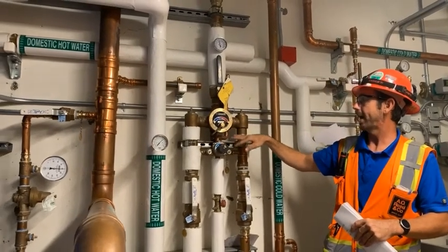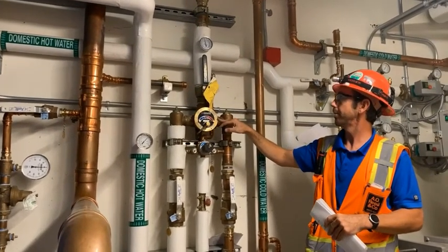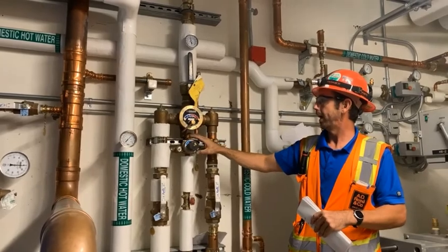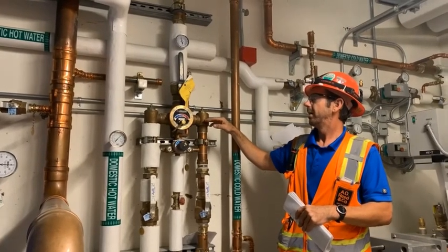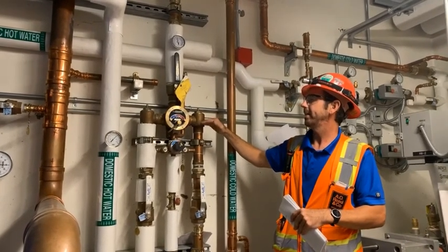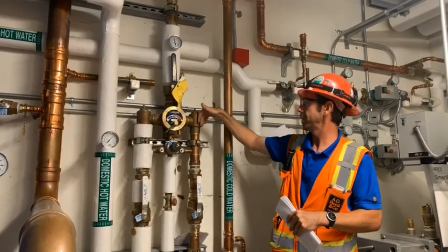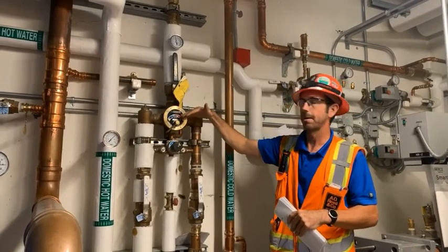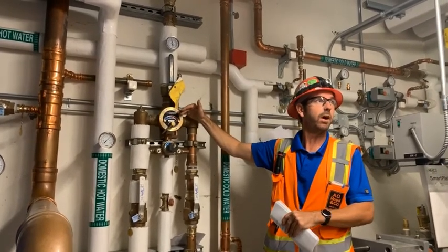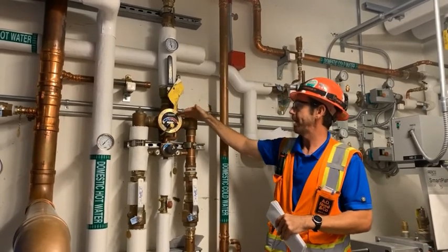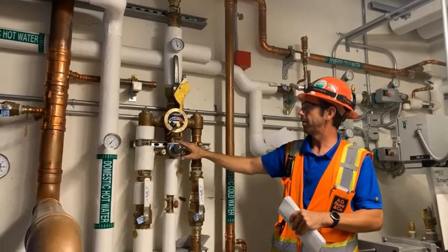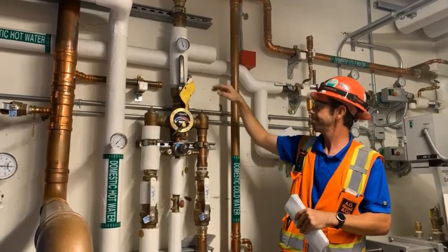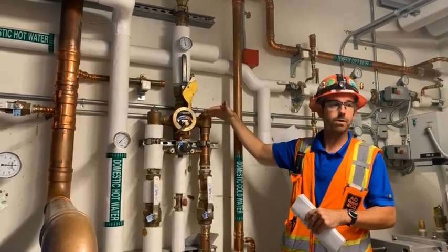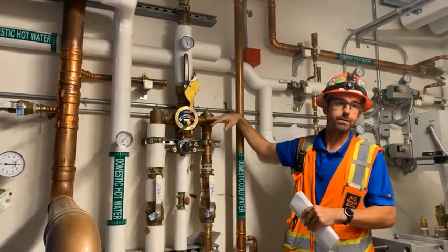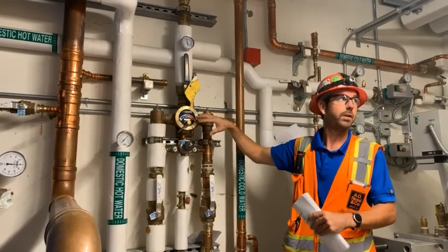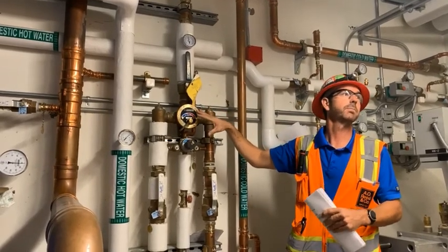This is kind of set up as a high flow, low flow thermostatic mixing valve. Under, I believe it was 18 GPM, there's spring checks that are pushing down on this upper regulator, okay? So if you don't have enough flow, this main reg will stay closed and all the flow will run through this one out to the system. Once you reach that flow rate, the main springs will be lifted open and you'll have flow through both. They're both set the same and they have to be both set the same.